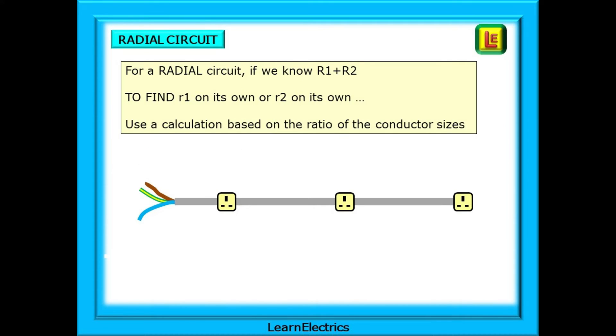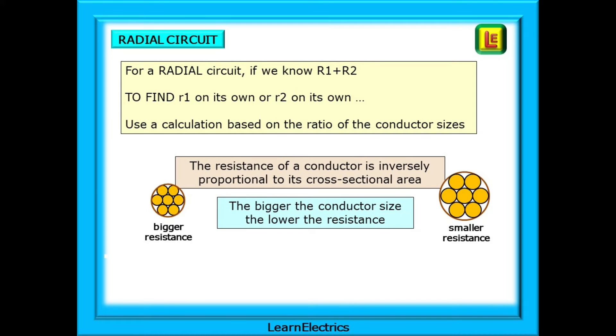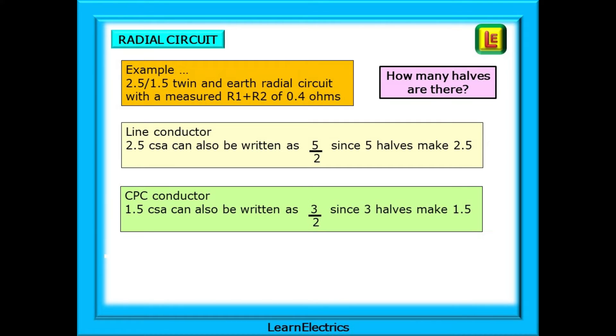For a radial circuit, if we know the resistance value of r1 plus r2 and want to find r1 or r2 on its own, we must use a calculation based on the ratio of the conductor sizes. We must understand that the resistance of a conductor is inversely proportional to its cross-sectional area. In other words, the bigger the conductor size, the lower the resistance, since there is more copper to carry the current. And if the conductor size decreases, the resistance value will increase. Let's work out an example.